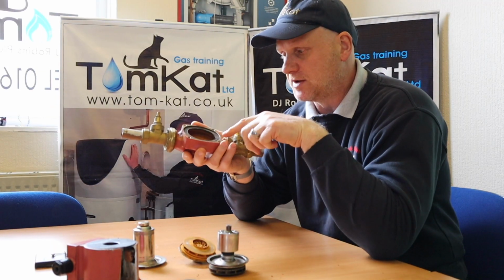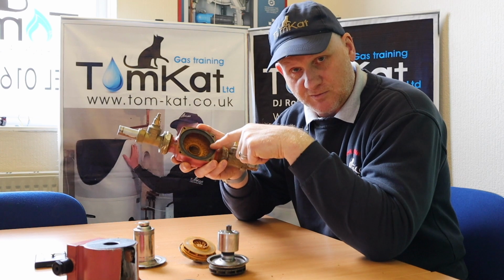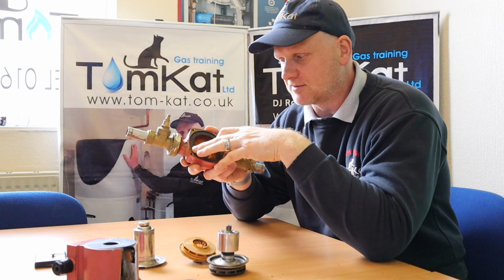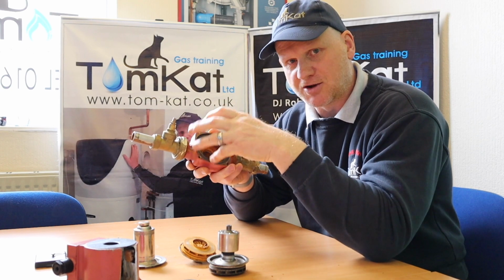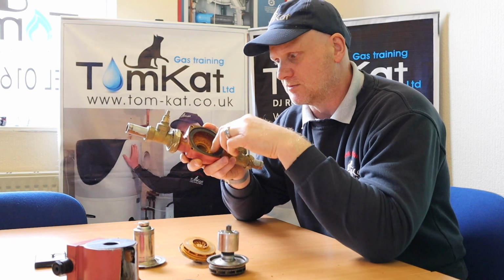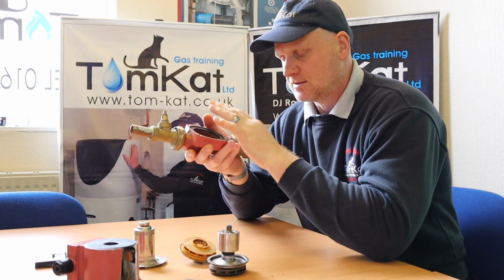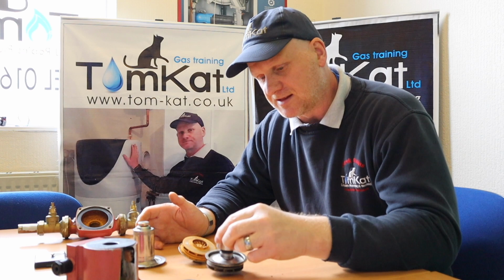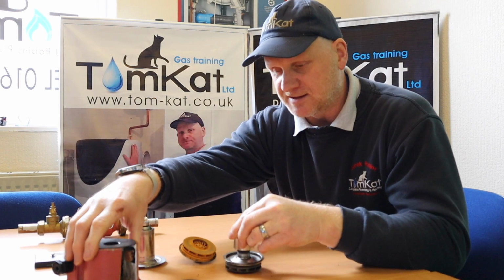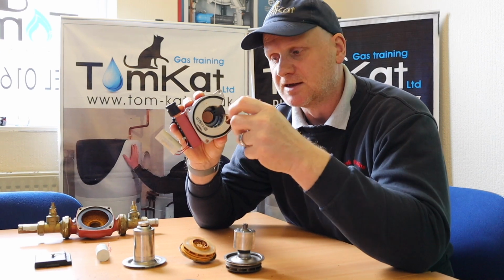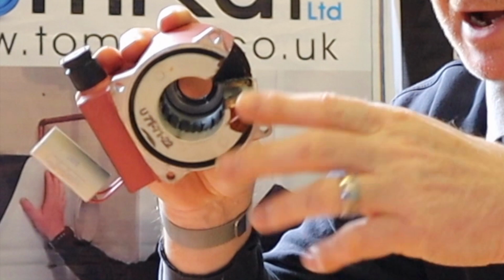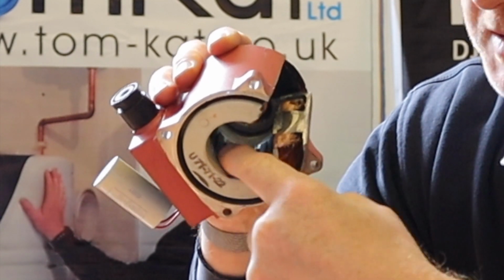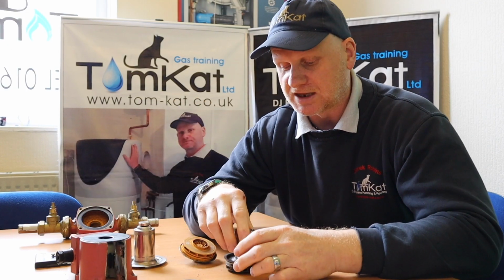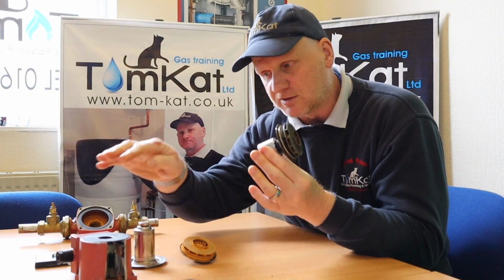Now we've had a look at the body. The only other thing to look at on the body is this rubber seal, and what Grundfos say is they'll guarantee that'll reseal if you take the head off. So you shouldn't have to remove that seal if it's in a good condition. So that's the seal in the body. Now the way the head is made up, this is the magnet rotor here, and this is the stator in the head. So this is the windings, so the copper bit there you can see is the windings. So you can see the little stator parts inside there, and what that does is it puts the power to those making a circle, which allows this now to rotate around the head.